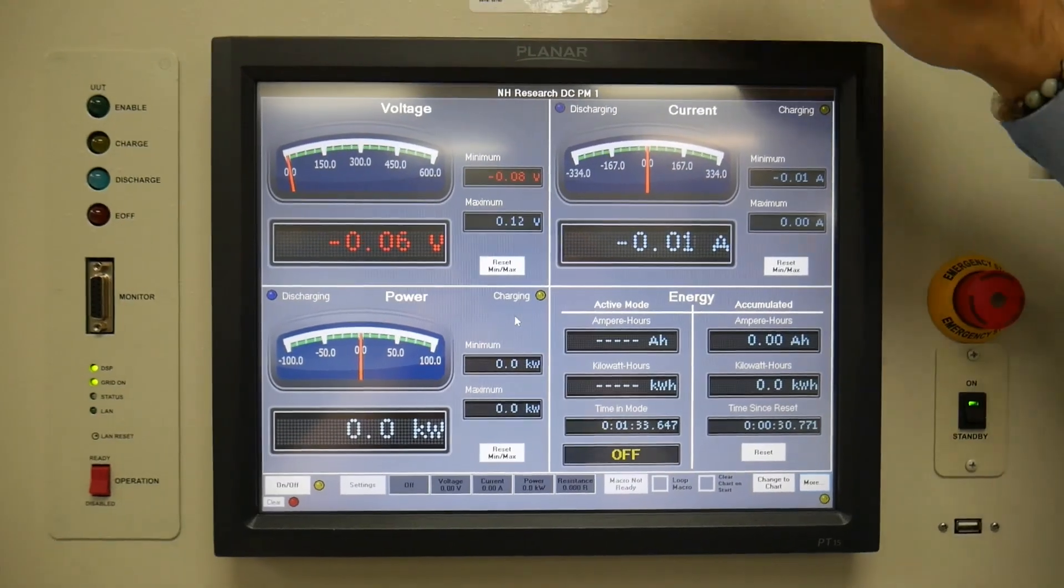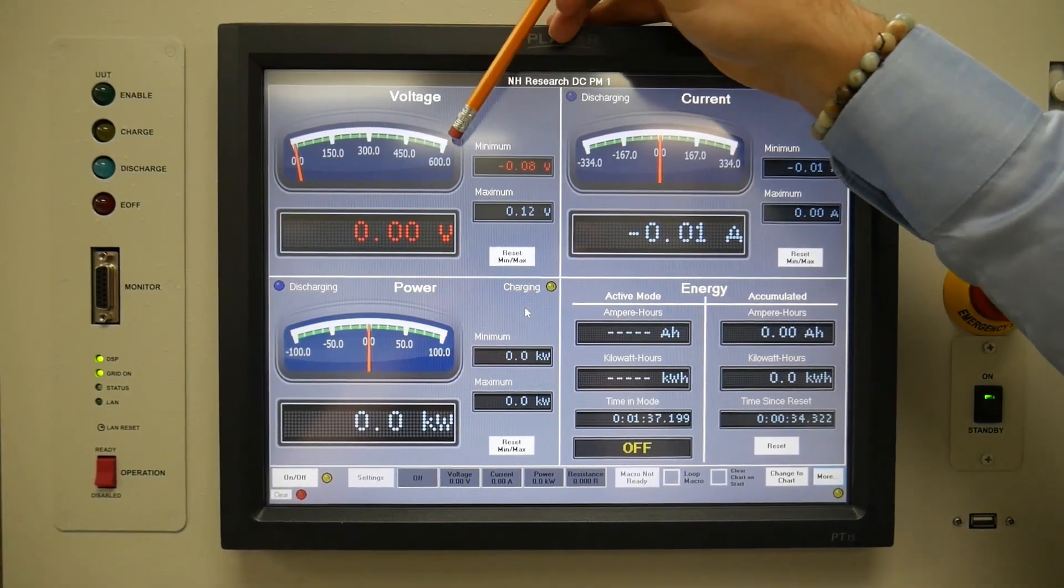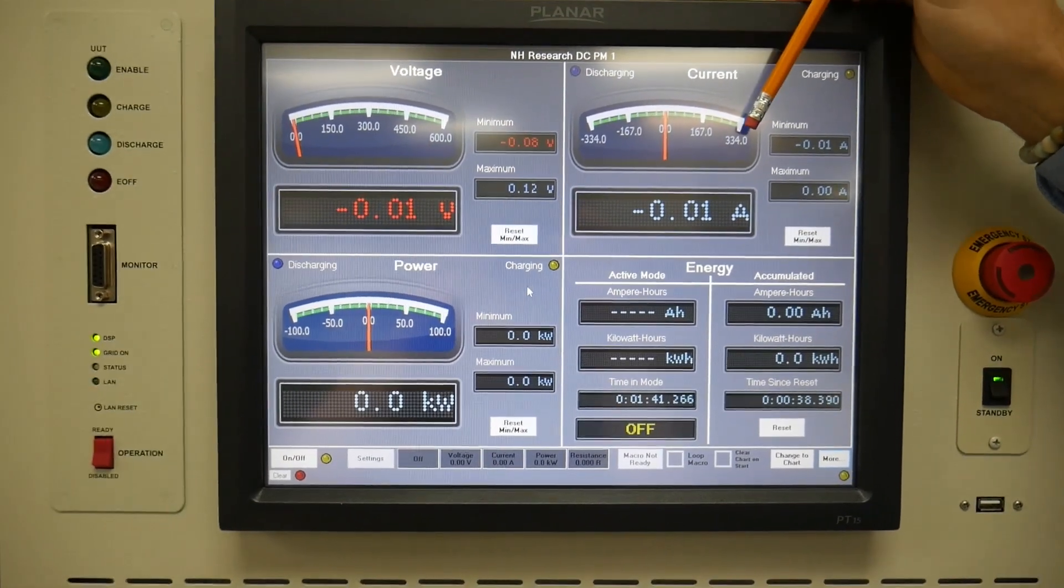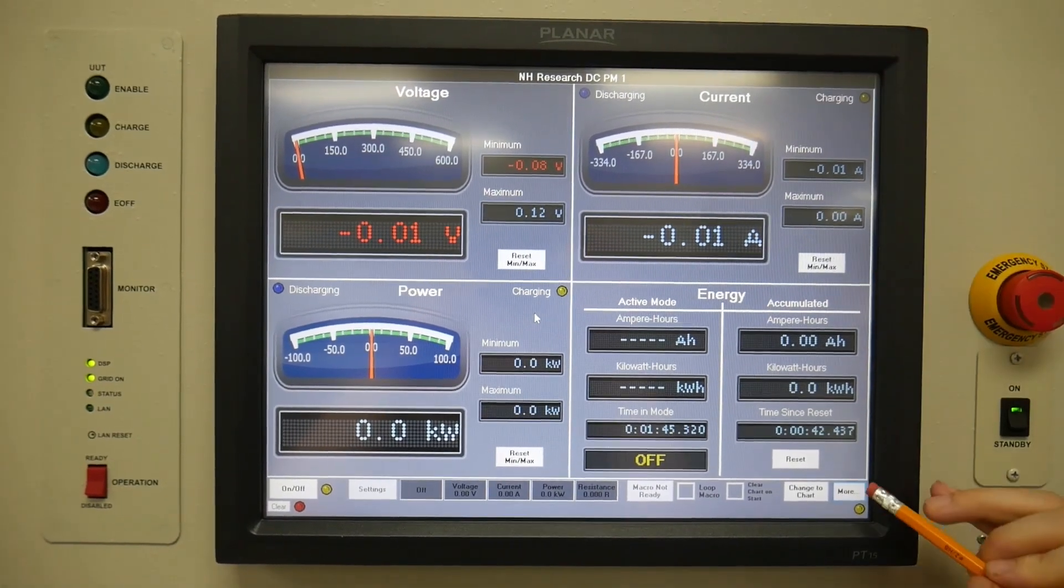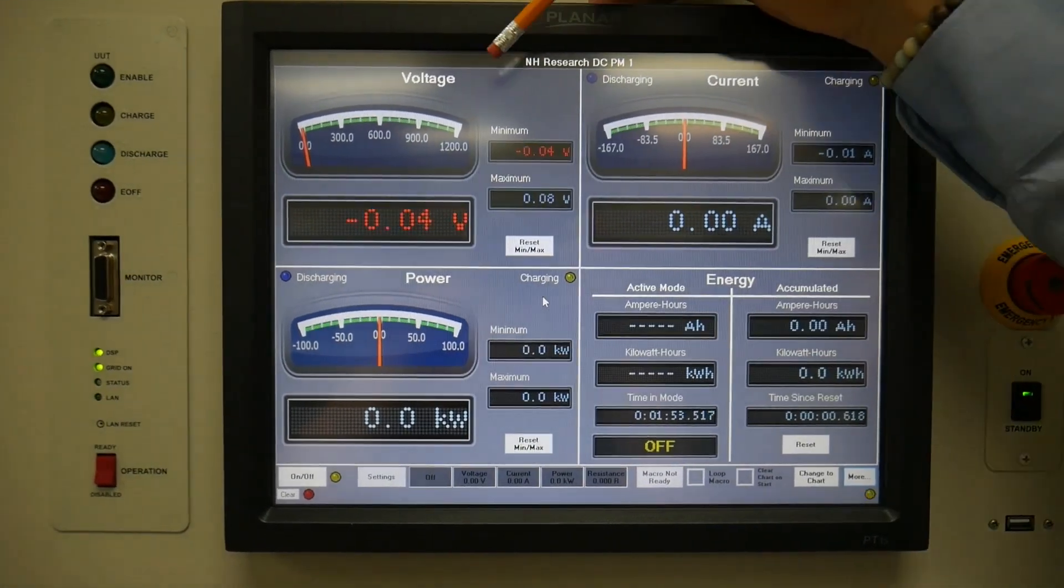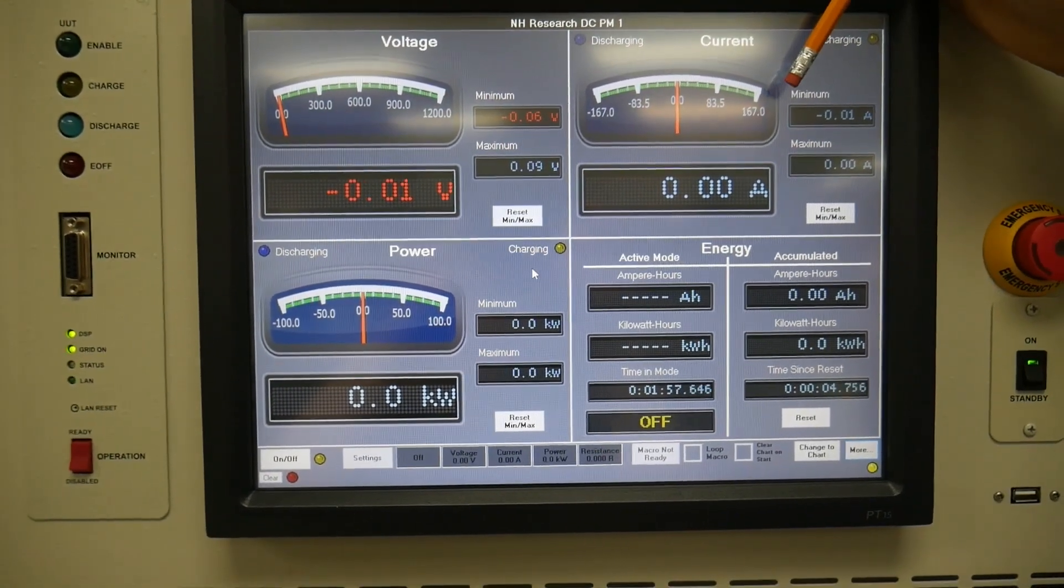So each cabinet is capable of 1,200 volts. Right here you see it only goes up to 600, but that's because your current can go up to 334 amps. To adjust that you can hit more, set operating range, and change your voltage to 1,200 volts. Hit OK. Now you have up to 1,200 volts and 167 amps.